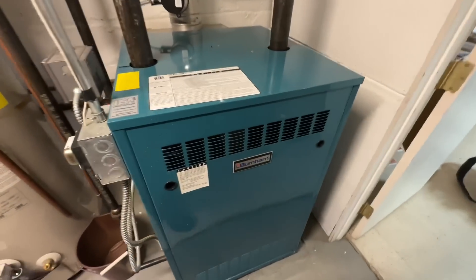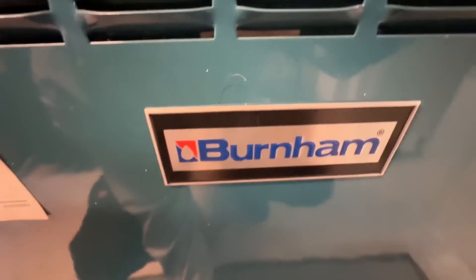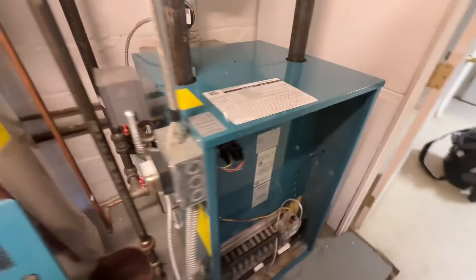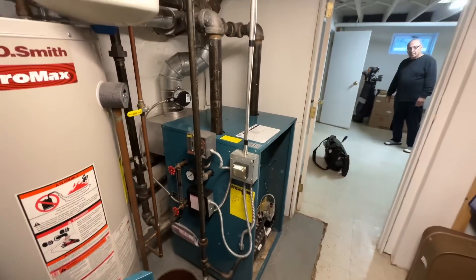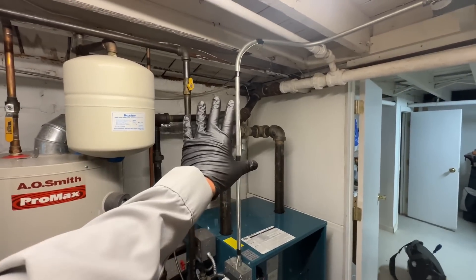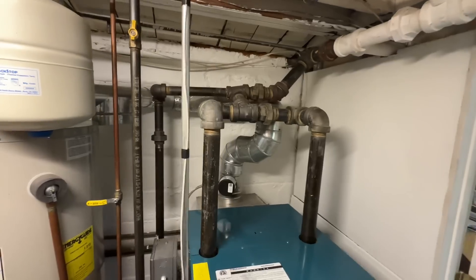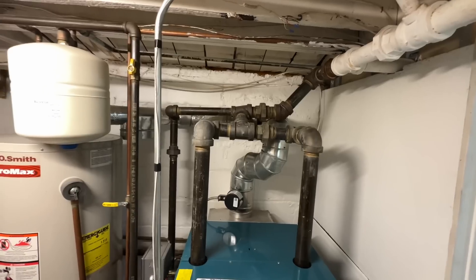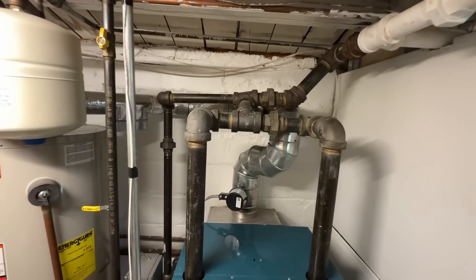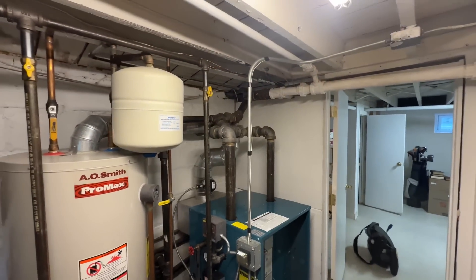We've got a Burnham — this is a 206, 175,000 BTU gas-fired boiler. Today we're not only going to insulate all this, but we're going to take out this mess and make it the right way. This header is done wrong, wrong, wrong, wrong, and we're going to take it out and redo it using the Viega Megapress.